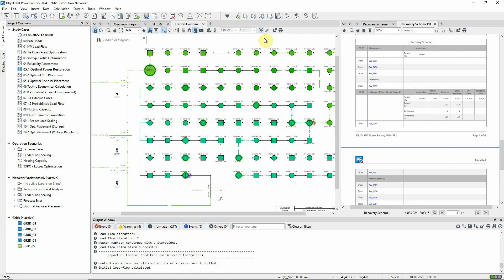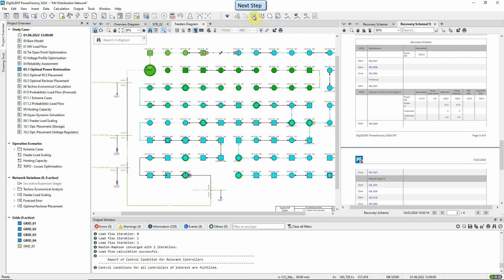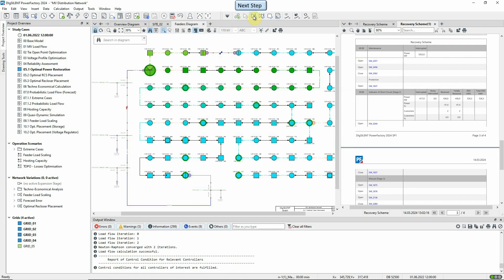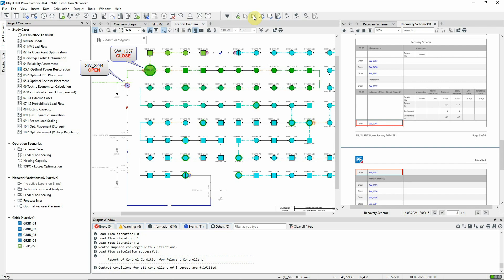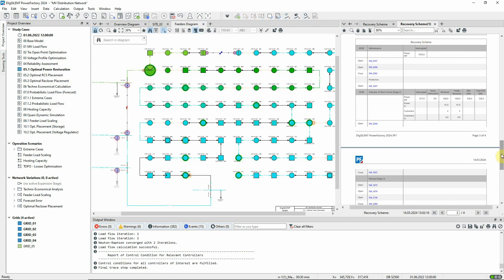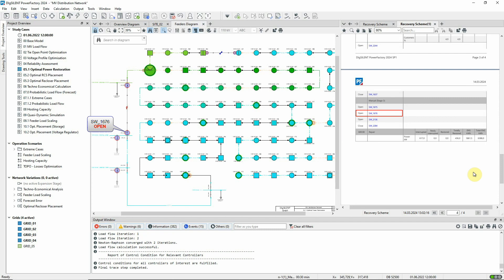We start again with the initial load flow. Then in the second step, the planned outage is applied. Already we can see that this has depressed the voltage levels in the area. Now the fault has occurred and as before, circuit breaker SW1637 opens. And again in the next step, SW2244 opens, which then allows SW1637 to be reclosed. As before, SW1676 is opened to complete the isolation of the faulted equipment and SW2284 is closed to resupply the loads.